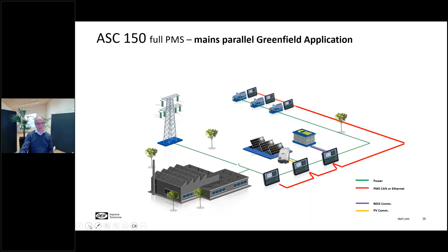The main purpose, again, is to maximize renewable production. Since we have full control of the generators in this setup, we can also offer spinning reserve support - it can be dynamic with the Fronius system, but also fixed spinning reserve if your load demands this. So we have fuel saving, running hour control because we control start and stop of generators, and a fuel optimizing mode that will rotate the priorities of the generators depending on the load size and the size of the actual generators. And then of course we can stop all generators when it's needed.